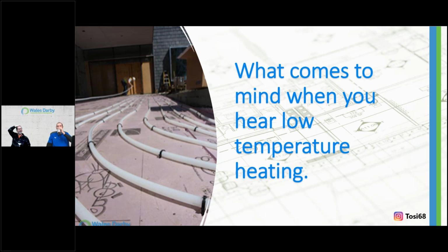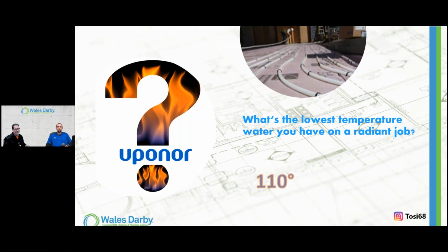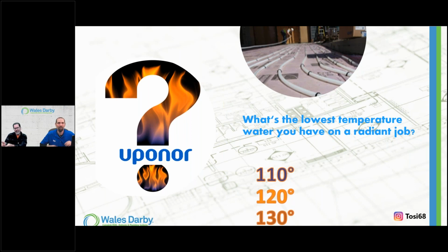So this went back to an earlier portion. Again, my slides are out of sync with the conversation, but what comes to mind when you hear low temperature heating, right? We're always comfortable with lowering water temperatures for radiant, right? And what are those temperatures? You can say, we could do 110, 120, 130, no problem, right? It's okay here, but anywhere else, it's got to be 180, right? And that just seems to be the fear factor, the horse blinders, right?